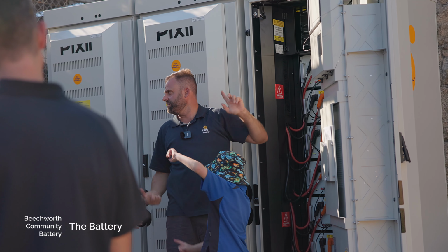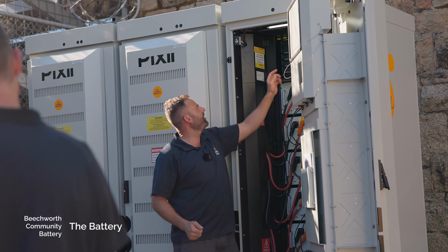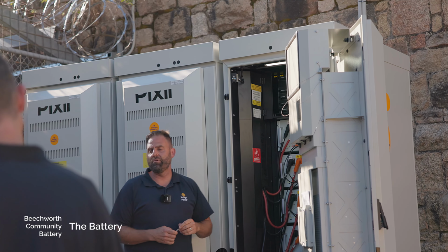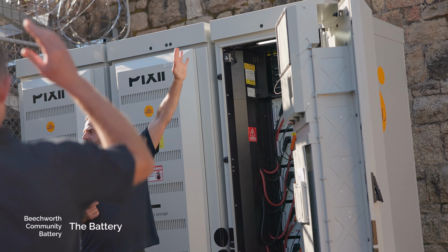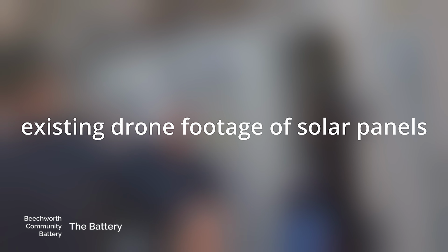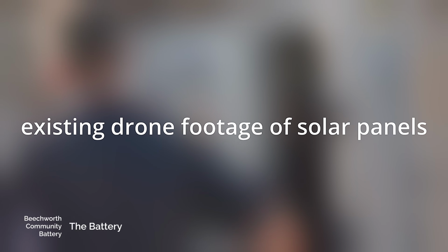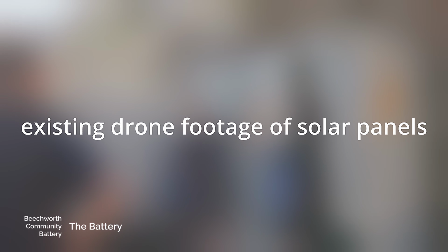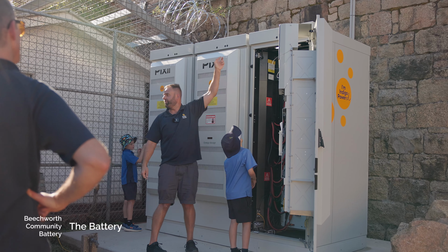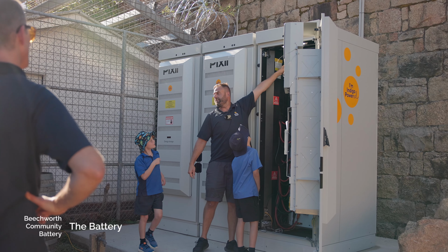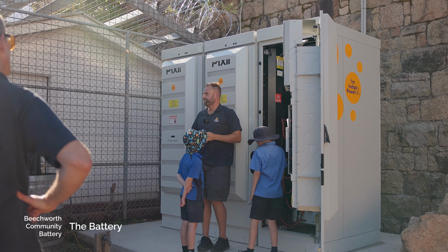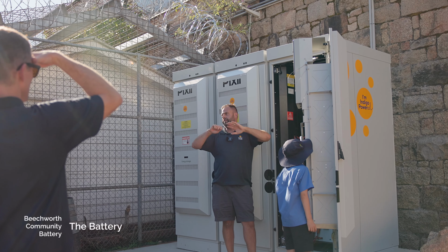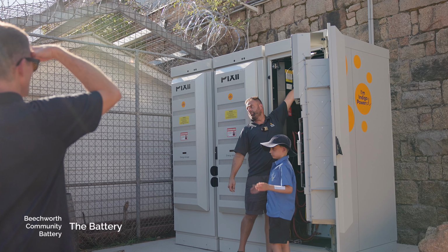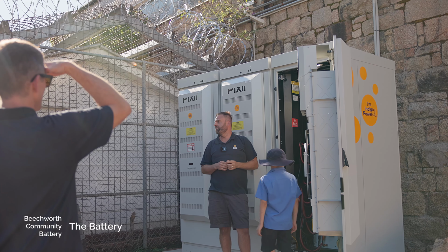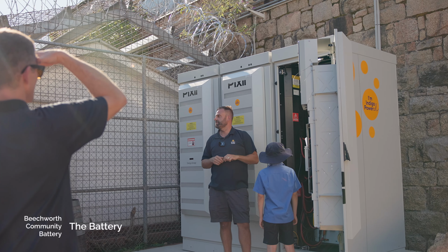This system is also the first integrated DC coupled system of its kind. We now have MPPTs up the top - we have 30 kilowatts of solar over there that's about 8 years old, and 35 kilowatts of solar over on the cafe. Those are what we call AC coupled to the battery, so they use the existing network to charge the battery. But what we have on that roof is 35 kilowatts of solar connected directly via DC current to the batteries. When the grid goes down and it's isolated, the DC coupled solar can charge these batteries without having to use the existing AC network in the jail.